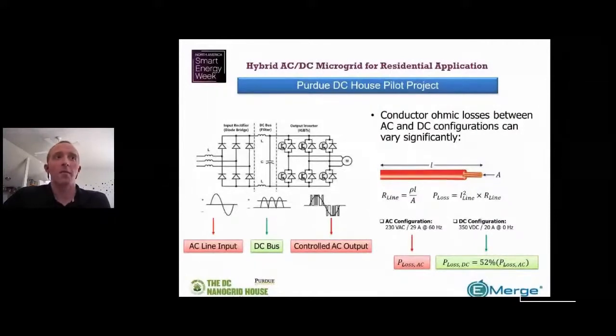What we want to do is bypass the AC input, the rectification, and power factor correction—all of those input stages—and just directly feed DC into the heat pump, directly into its control circuits. In doing so, we believe we can save a non-trivial amount of energy in the long run, especially considering 50% of energy costs come from this unit alone. So saving even a few percent by avoiding conversion losses can add up in a big way over the course of the year.